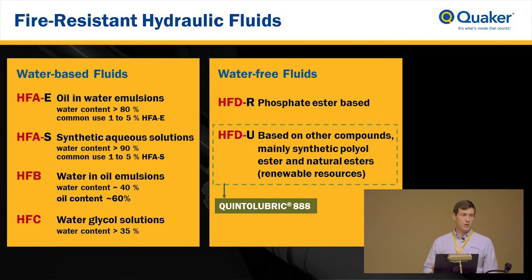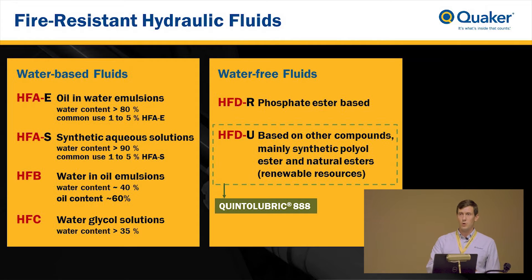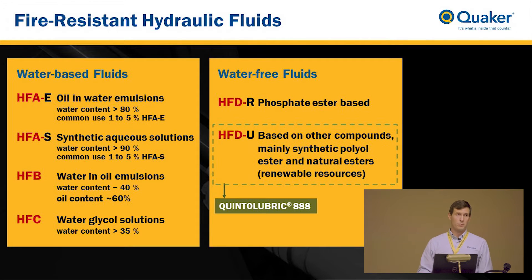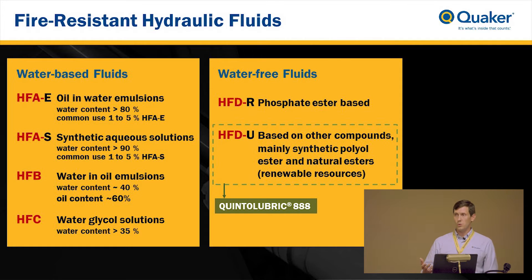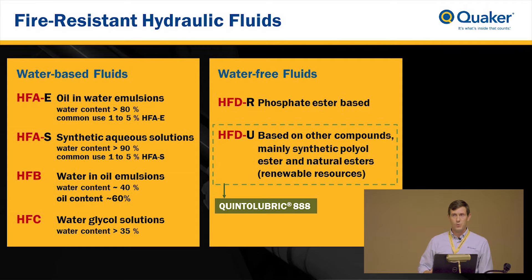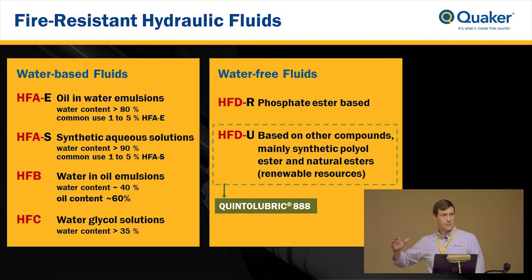HFA fluid is a regular emulsion. A lot of people call this 95-5 fluid because it's 95 percent water and 5 percent oil. The second is HFB, an invert emulsion — the opposite, about 40 percent water and 60 percent oil, putting water into the oil. HFC is a water glycol type product with about 35 to 45 percent water content. All of these on the left side are water-based hydraulic fluids, so most of the fire resistance comes from the water.